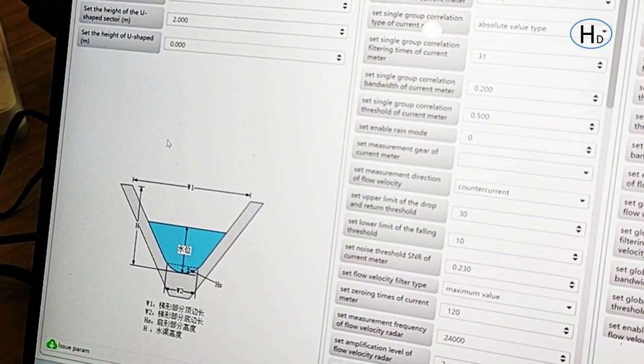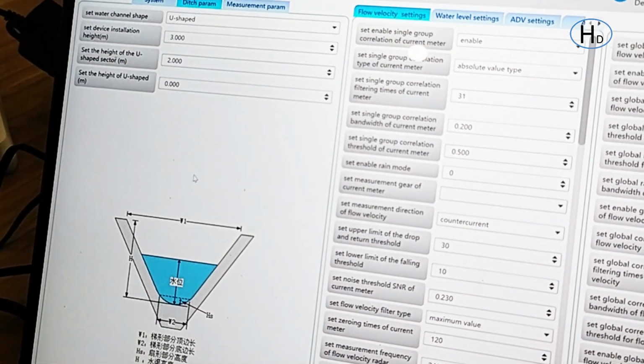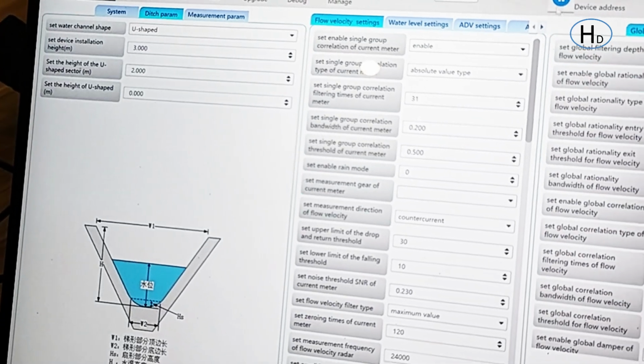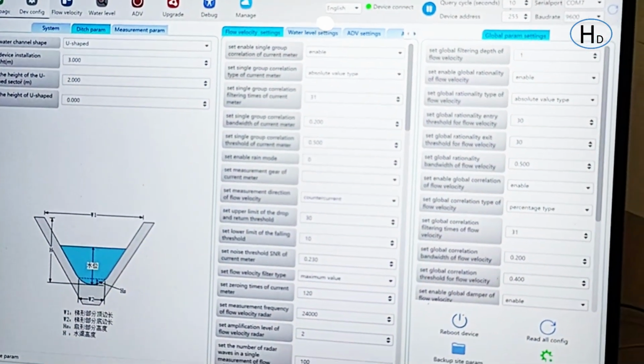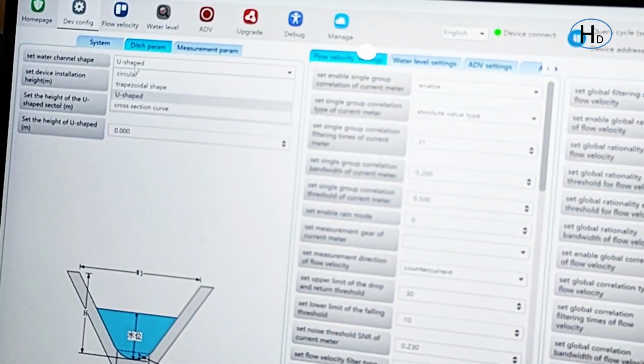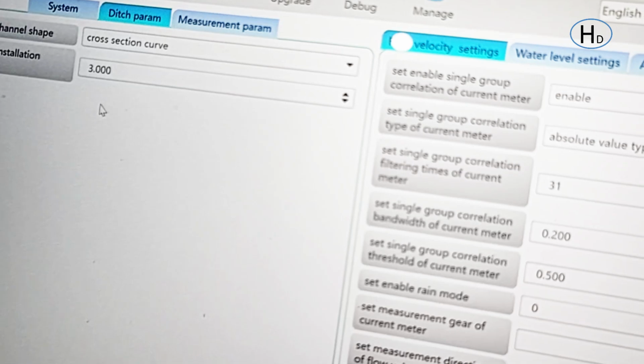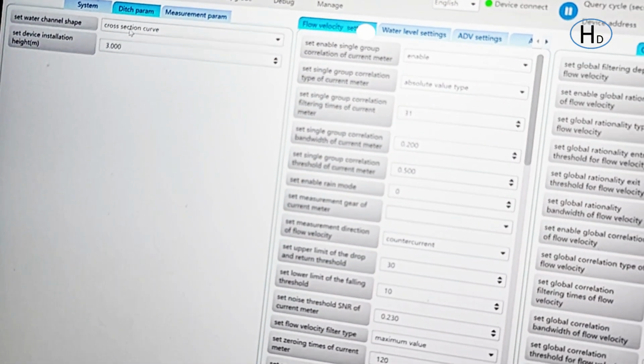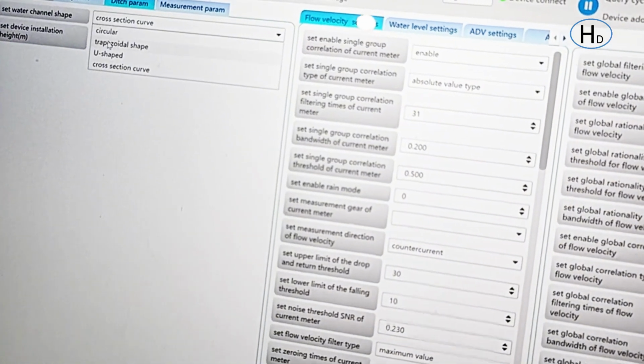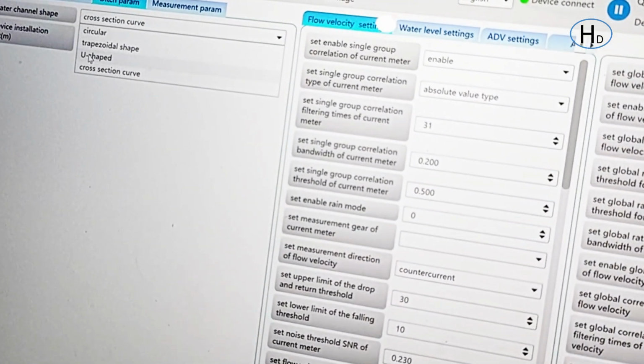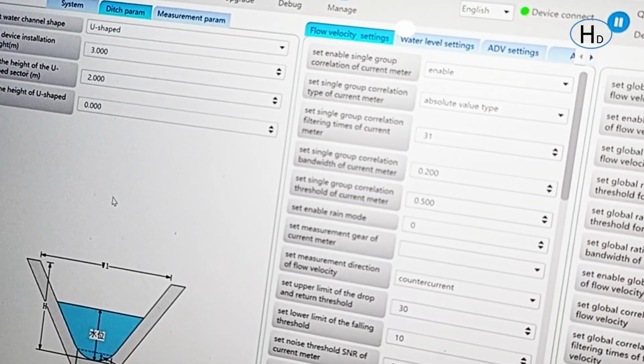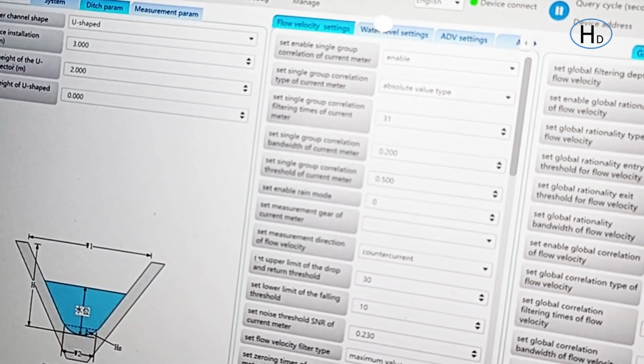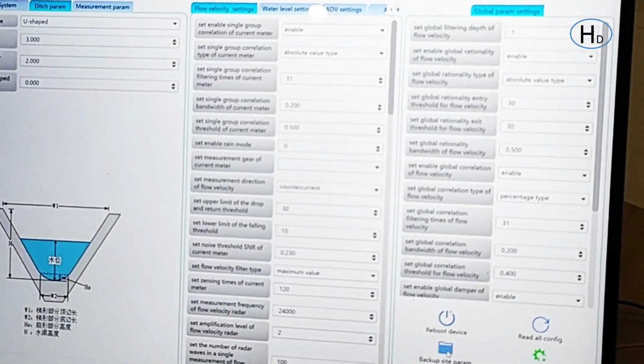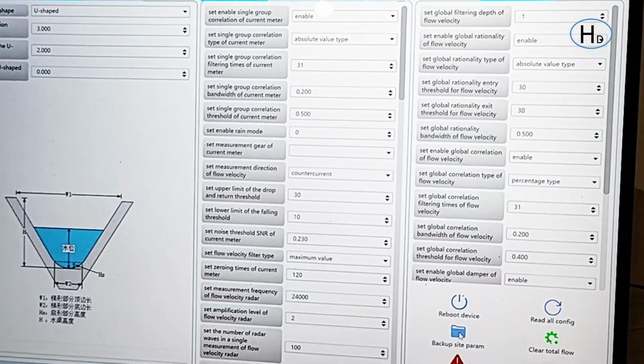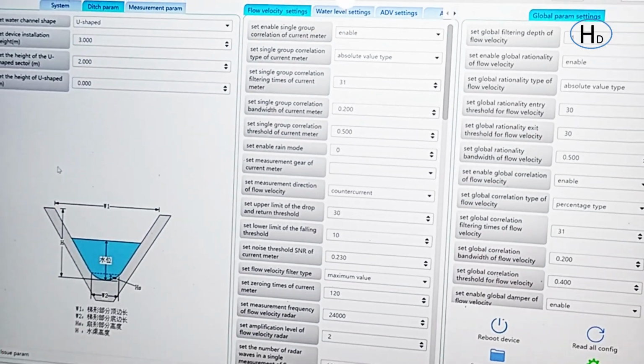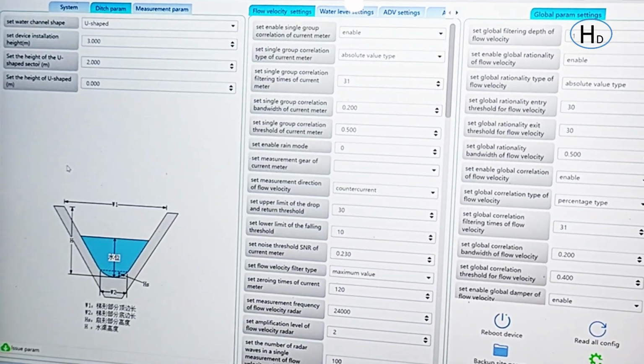So that is the config of the radar sensor. After that, please don't change anything of them. Just make the config of this one okay. And you choose the tab. Also, in this one you can set the cross-section curve. Normally you use these three tabs. You just set the three tabs and then set the related parameters, and then it is okay. And after you set all of them, you must click here, backup site parameter, and then all of the parameters will be stored in the sensor. And that is how to set the sensor.